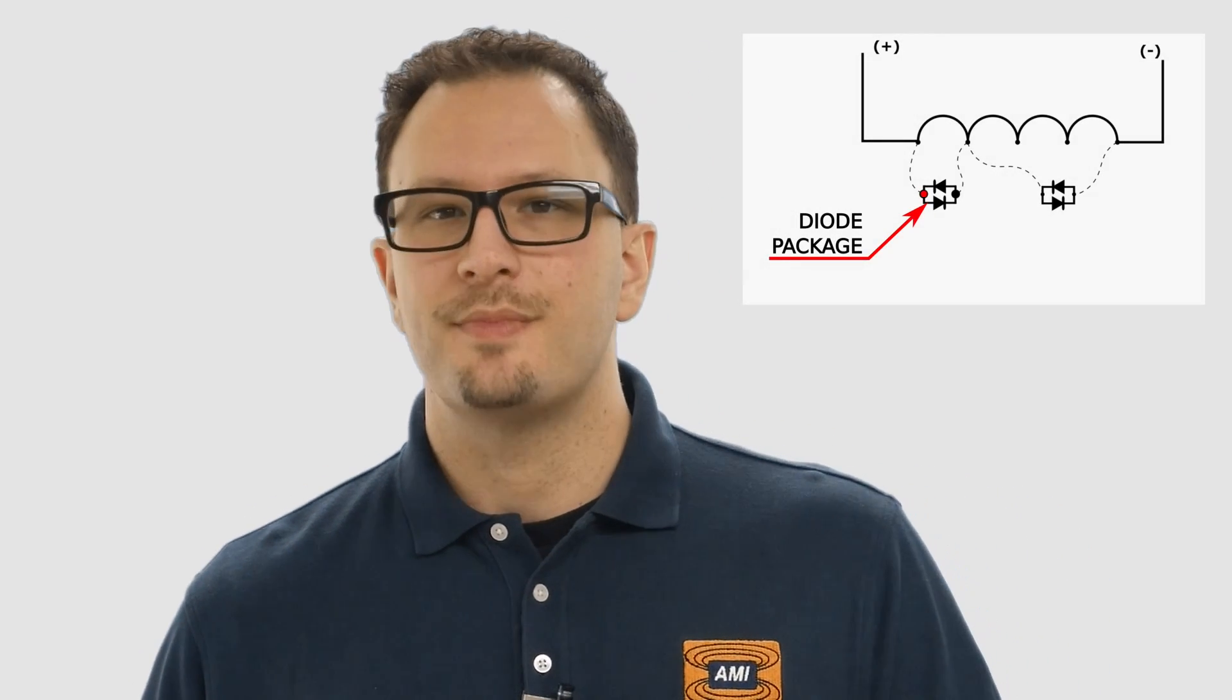These protection diodes are a package of two diodes connected in anti-parallel, which is basically anode to cathode. Depending on the size of your magnet, you could have one diode package or you could have several.